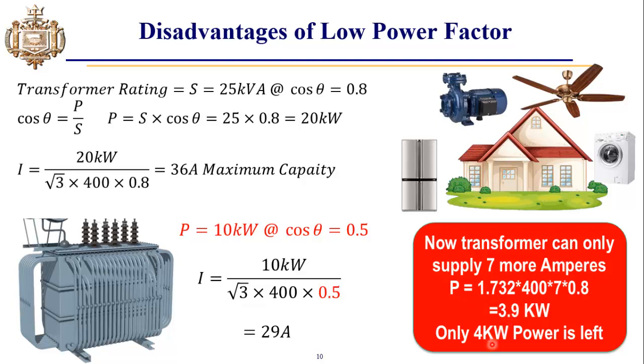What we infer from this information is that we are only drawing 14 kilowatts of useful power from this transformer, and the rest of the power, which is 6 kilowatts, is wasted due to the poor power factor.